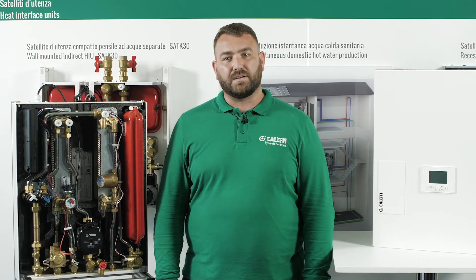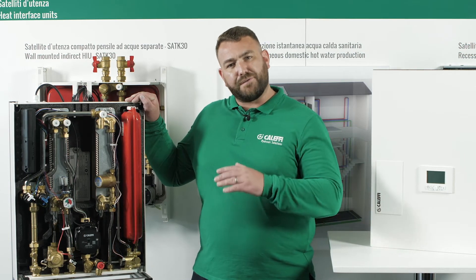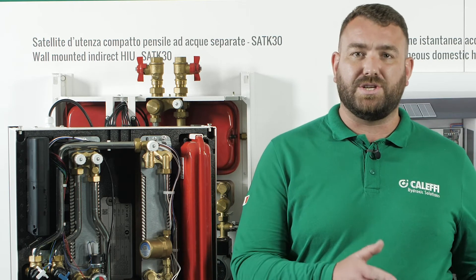The hot water coming into the HIU should be used to such a degree that there is a far cooler temperature returning to the heat source — this is called the delta T. The bigger the delta T, the more efficiently the energy is used, benefiting the overall system.